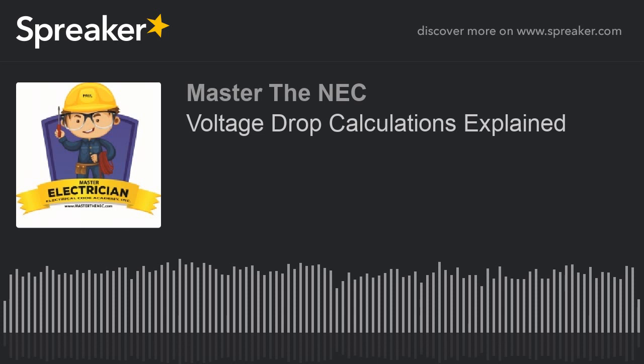The decimals really aren't going to matter in this case. It's still 7.9% voltage drop. Okay? Not good, but that's what we've got. And again, you do the same thing, and if you wanted to find out what it is at 240, then you could. You just simply take those values and you will divide it by 240 instead of 120. Same concept. All right, so that's how you find it. You see that works out.